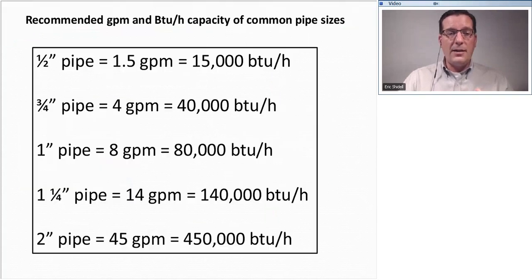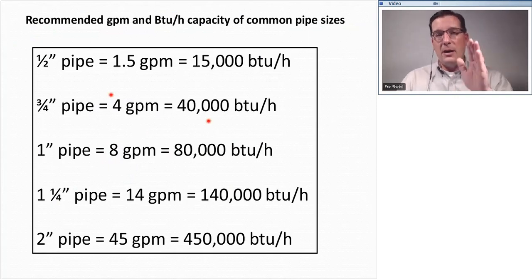The last thing we want to talk about today is some common GPM flow rates and BTU capacity and common pipe sizes. And this is kind of just for reference. So real quick, half-inch pipe, generally good for 15,000 BTU. Three-quarter pipe, which is pretty much the standard in all of our manifold series loop piping, 40,000 BTU per three-quarter inch branch. These are some of the rules of thumb that a lot of our systems were designed around back in the day.